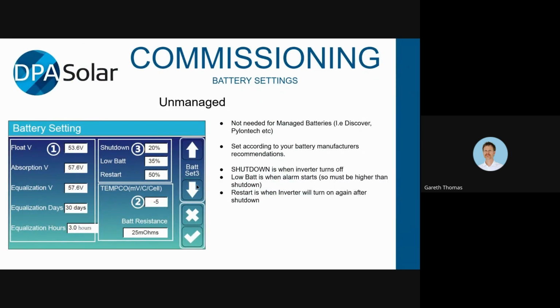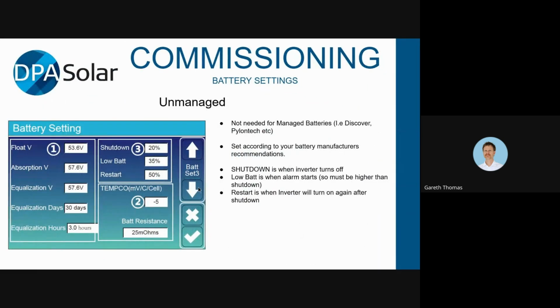Right. Once you've saved those settings, press the down arrow again. You're going to go through to the battery settings, page number 3. If you're using unmanaged batteries, this is where you're going to set all your battery charge voltages and equalization settings. So you're just going to set them according to the battery manufacturer's instructions. Not needed for managed batteries. You'll see a different page for managed batteries, which I'll show you in a second.